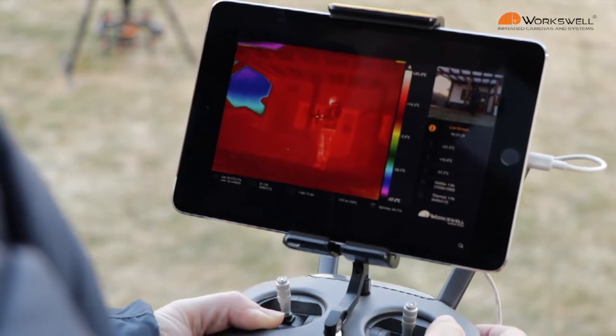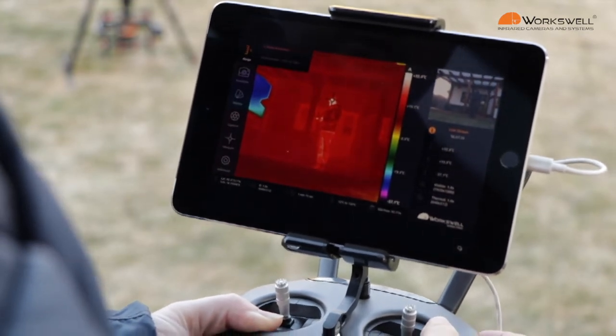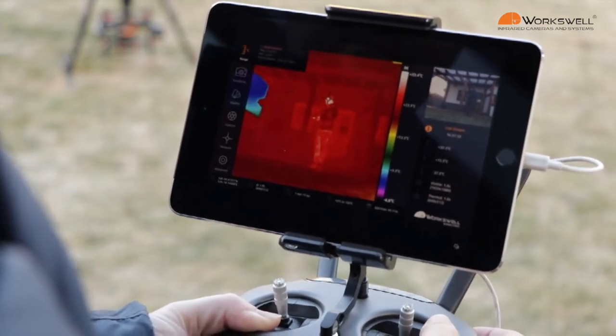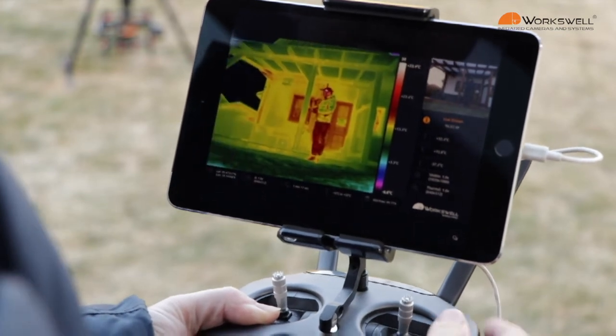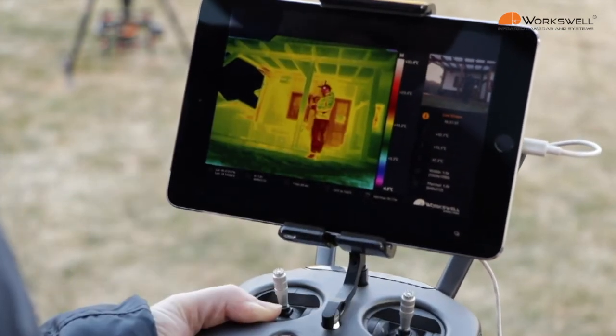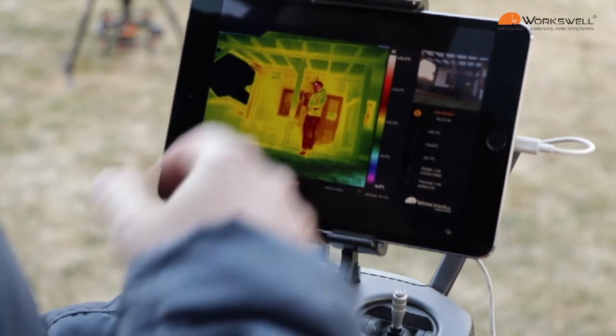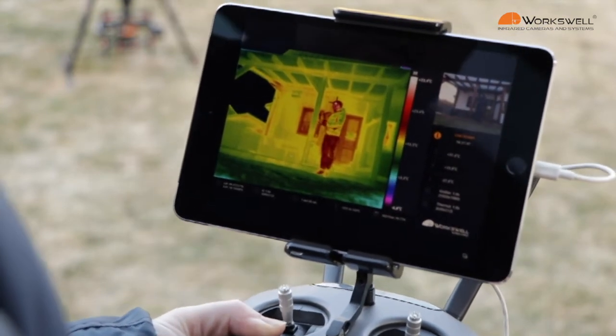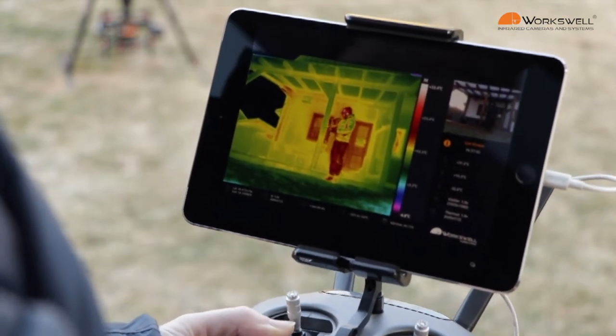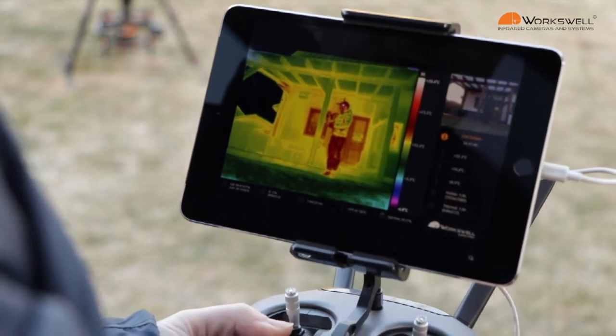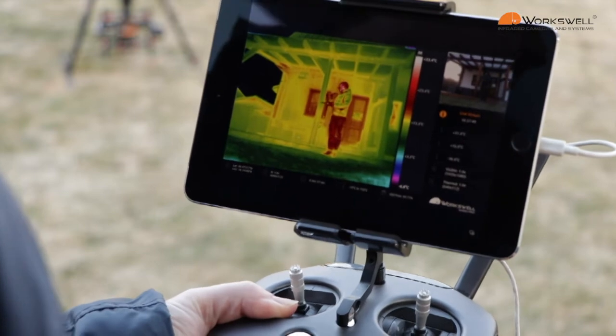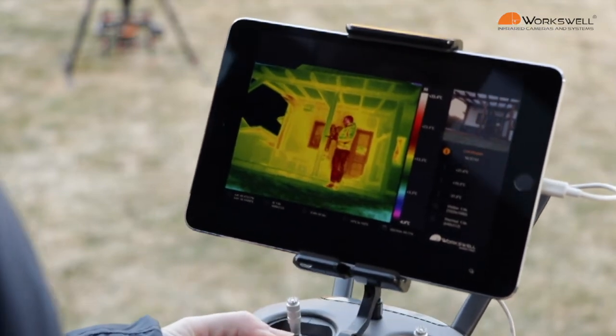So what you can easily do is to switch the manual temperature range on. And you will be able to see very very sharp image of myself and the house behind me. Without settings of a manual temperature range, it's very difficult to recognize me and find the leakage or the hot spots you are looking for.